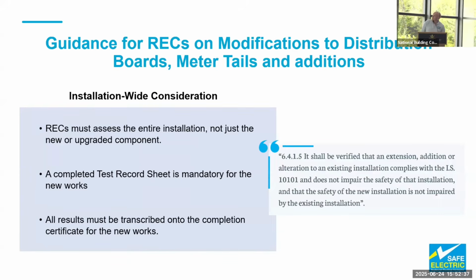The guidance again for RECs on modification to distribution boards and meter tails and additions. So again, the RECs must assess the entire installation, not just the new or upgraded component. So this is very important again. So I keep saying to electrical contractors, leave the tool bag in the van, bring in the test gear, and carry out your assessment of the existing installation first. Extremely important. A completed test record sheet is mandatory for the new works, and also for including the testing of the existing. All results must be transcribed onto the completion certificate for all new works undertaken by the registered electrical contractor.